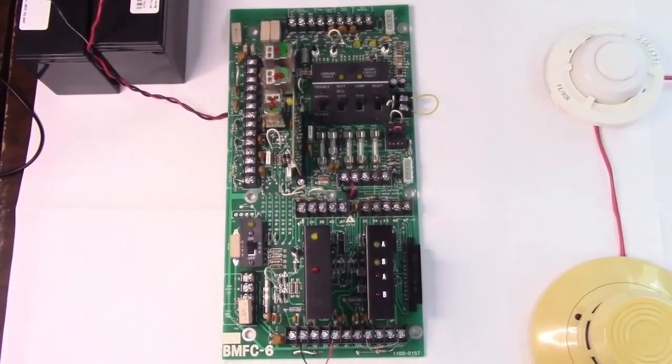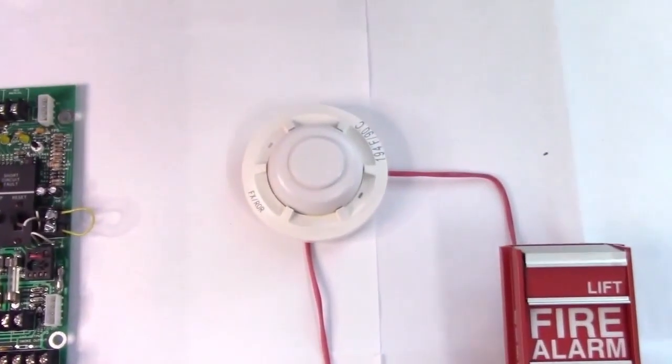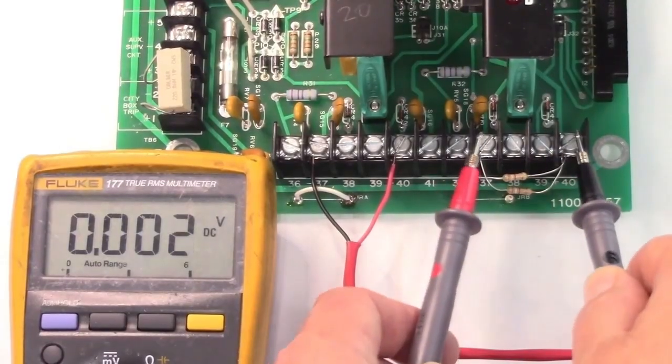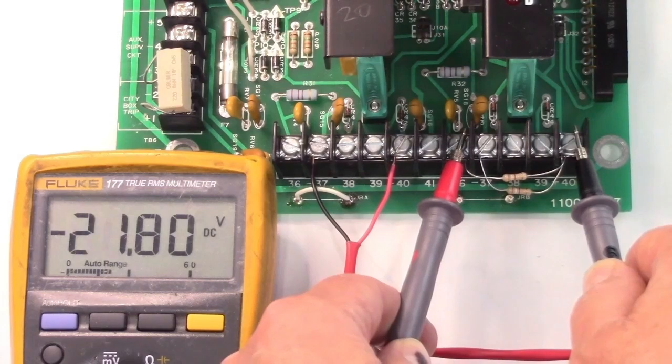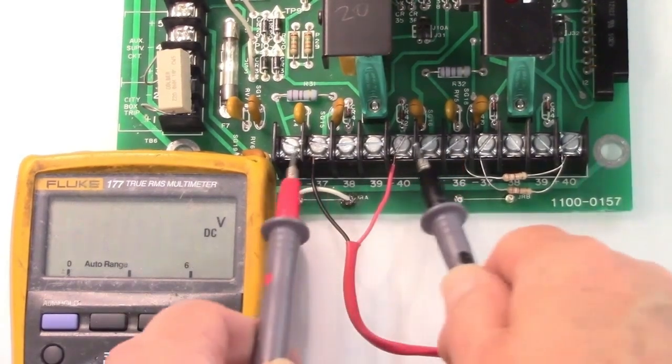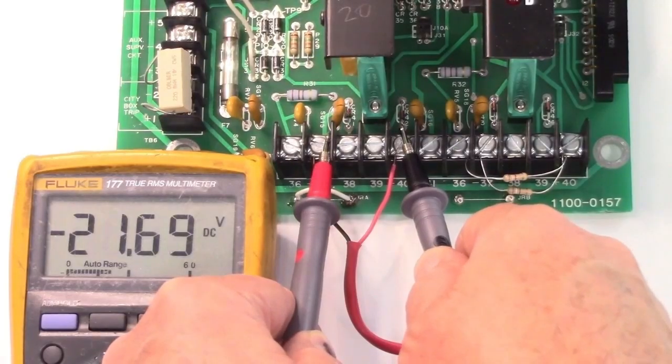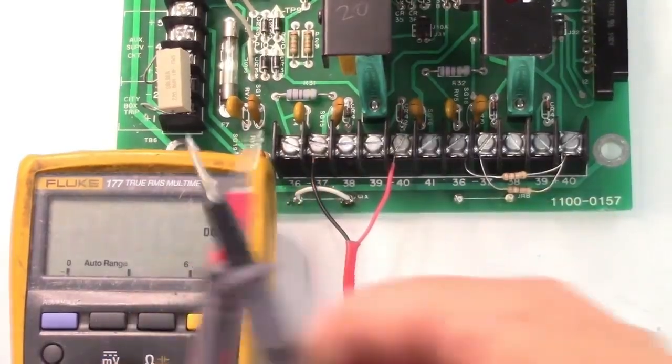This is a BMFC-6 main board and it's wired to a smoke detector, heat detector, and a pull station. The normal zone voltage across an end of line resistor is 21.8 on this panel. And if we measure the other one, we'll read a little bit less because of the additional current draw of the smoke detector. The more smoke detectors, the more current draw.